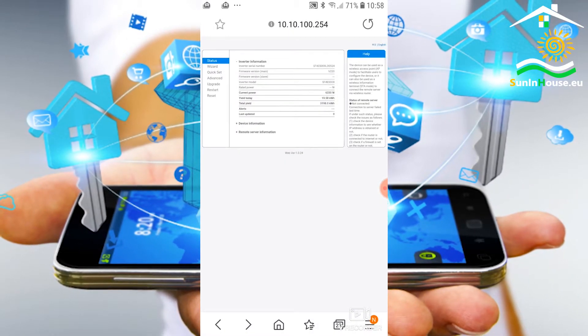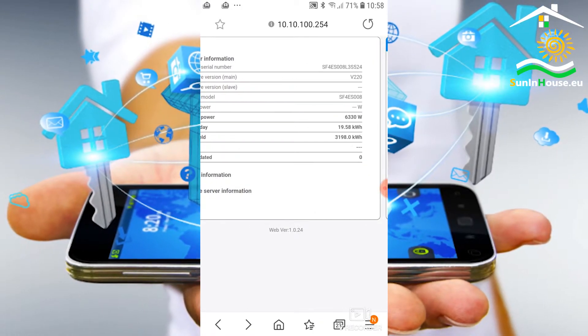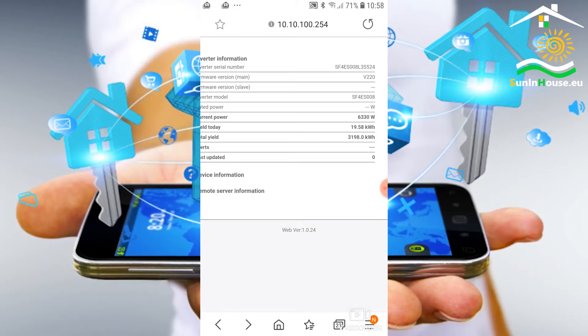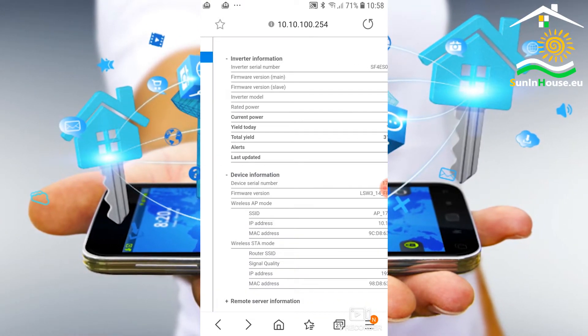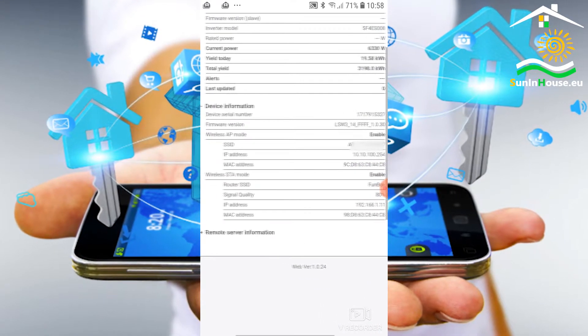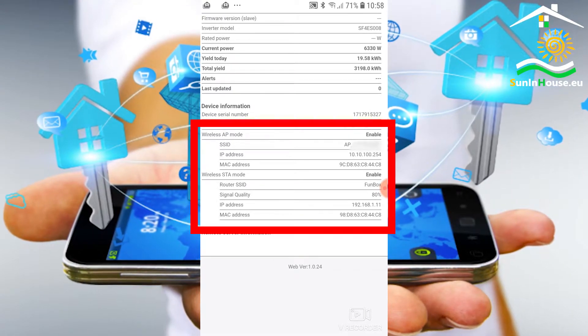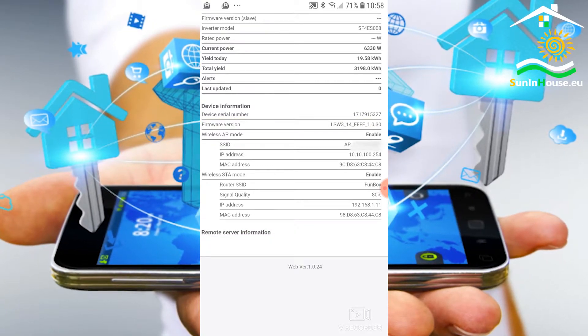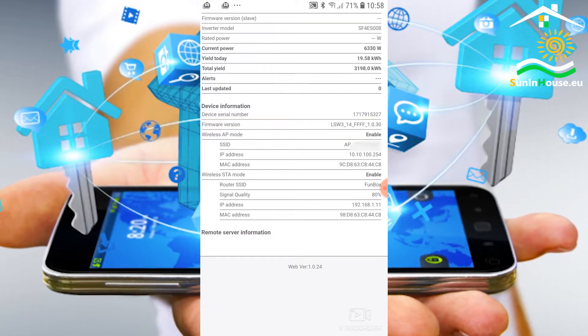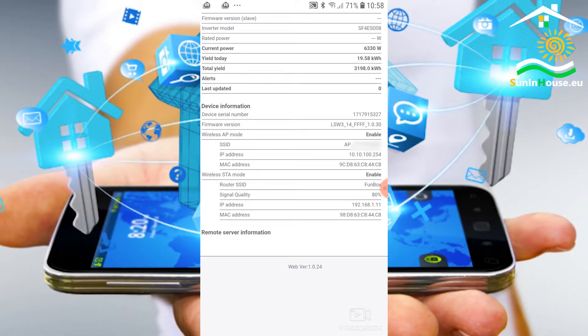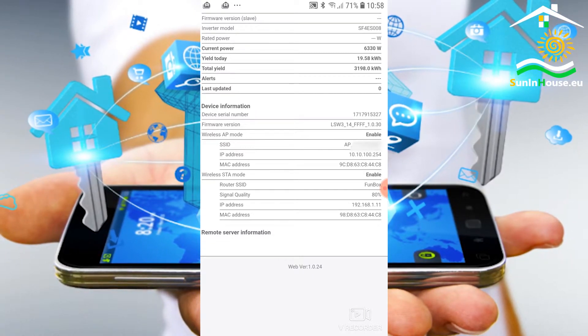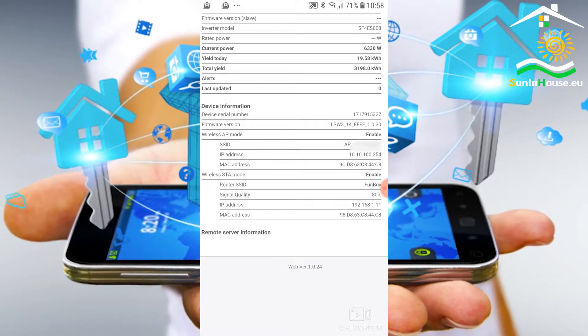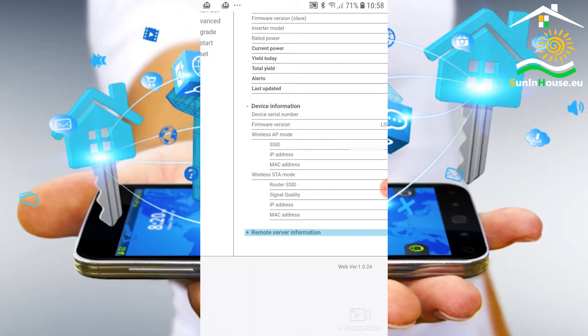Let's take a look at what we have here to make it all clear. We have the status, serial number, inverter number, current operating parameters. In the device information section we can see that both logger operation modes are enabled - both a station connected to our Wi-Fi network with the internet and access point mode. It is worth leaving this setting like this because in the future we can log in to the logger in AP mode. There may be a need if we want to change something.